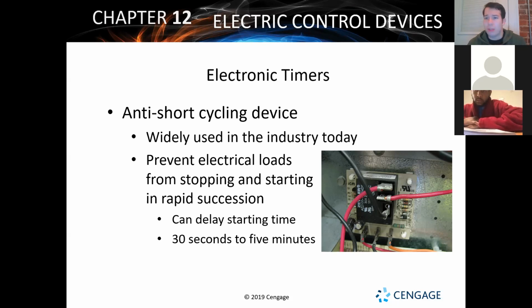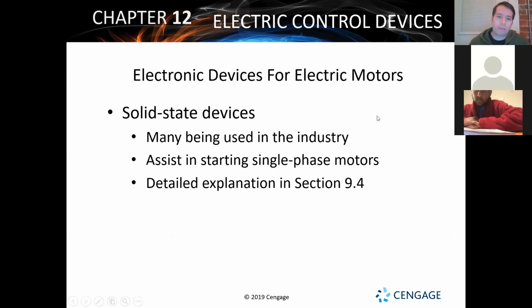So if you set your timers to 5 minutes and you start watching it, it kicks on at 4 minutes, it might have been only set to 4 minutes. But if you set it to 5 minutes and you wait for 5 minutes to go by, and nothing comes on, you know something else in the system is not working still. So at that point, you're not saying, oh, it's the short cycling device or the time delay that's causing it not to turn on. It's been 5 minutes. Something else is making it not turn on. And that's just an easy way to eliminate that from being an issue.